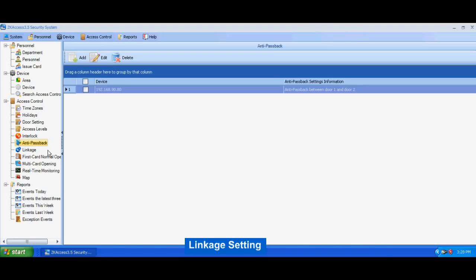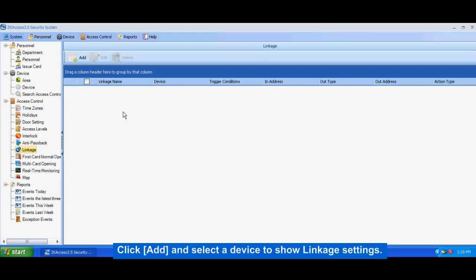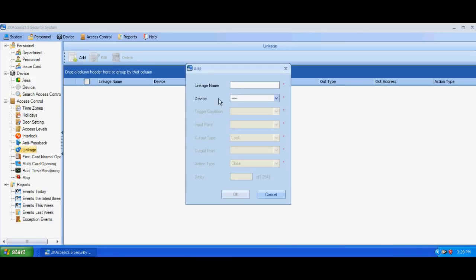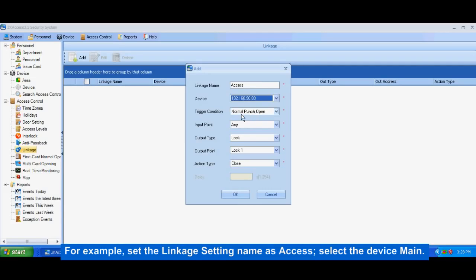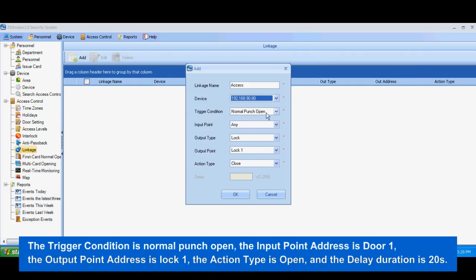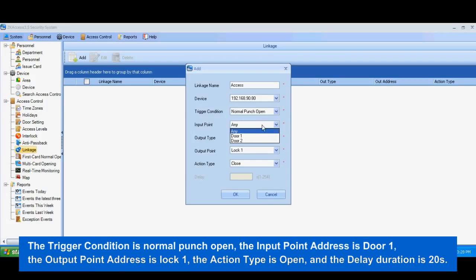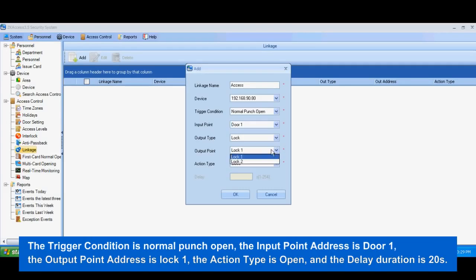Linkage setting. Click Add and select a device to show linkage settings. For example, set the linkage setting name as 'Access,' select the device 'Main.' The trigger condition is Normal Punch Open, the input point address is Door 1, the output point address is Lock 1, the action type is Open, and the delayed duration is 20 seconds.